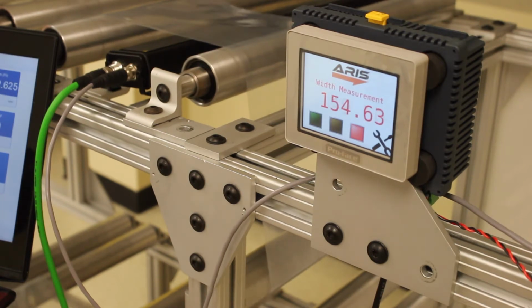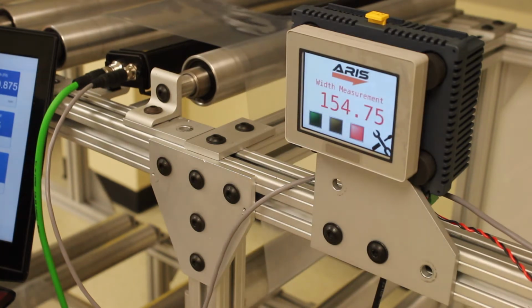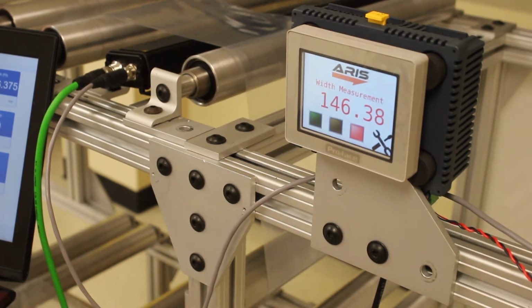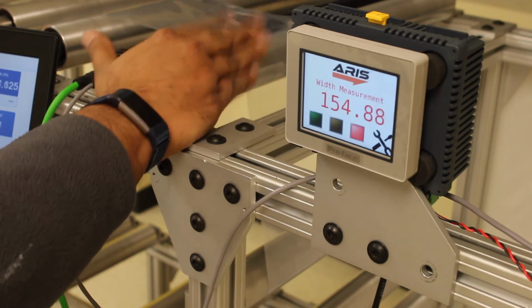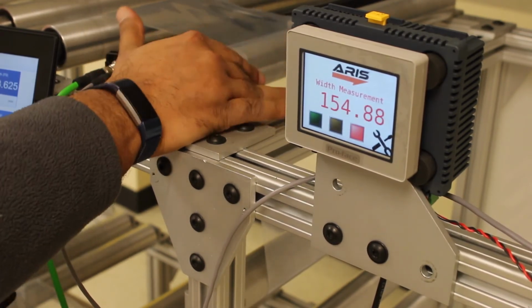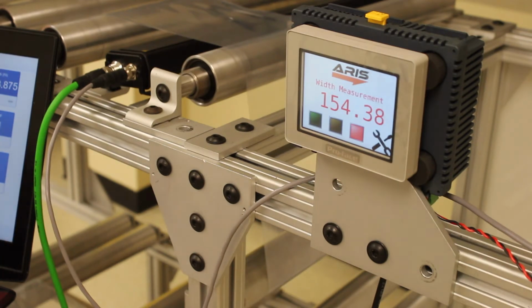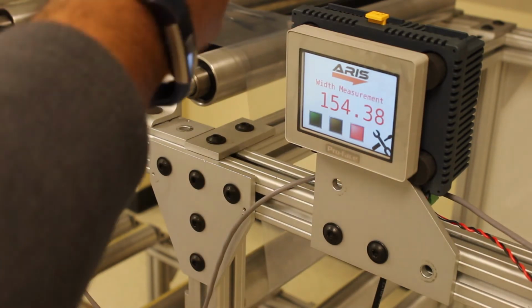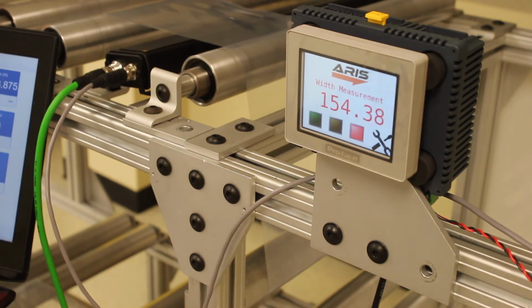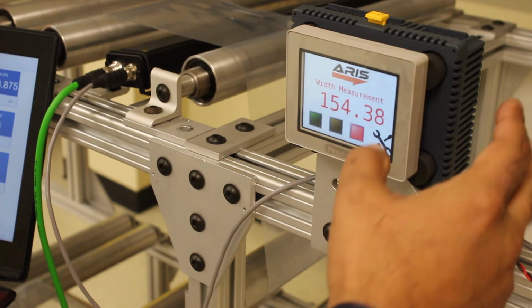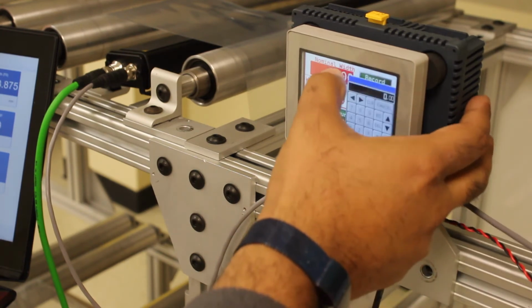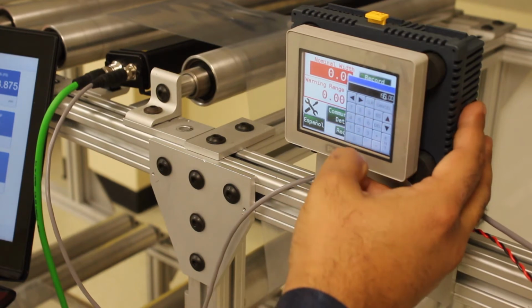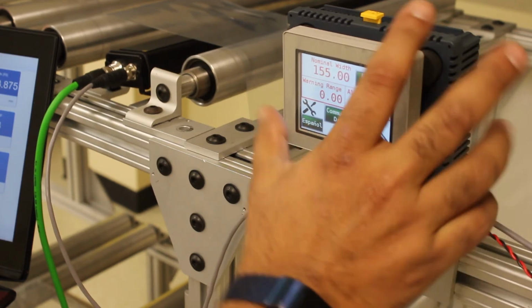Now, if the customer wants to set a few things, for example, if they want to teach the sensor so that we avoid any inaccuracies in the measurement, what we would do is put the web at the location where they desire it and measure the width of the web. Let's say in this case it's 155 millimeters. We would go in and enter 155 and press record width.